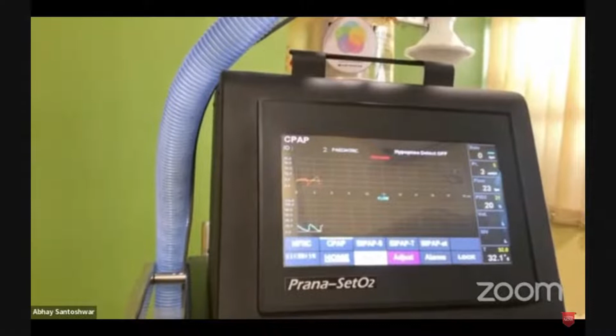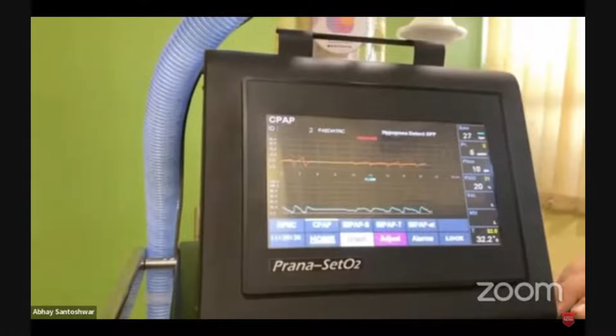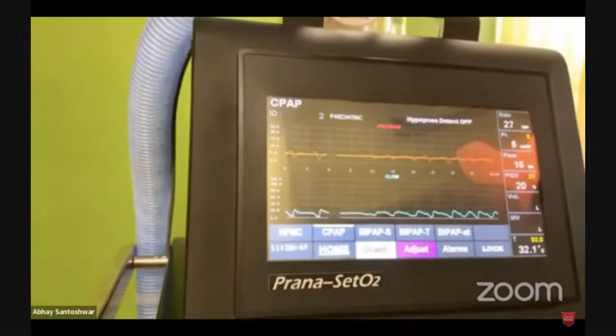So here again, the top waveform, the red one, is pressure and the lower one is flow. As the patient starts interacting, you can see the flows changing and the CPAP pressure diagram showing that it's trying to reach the set PEEP value. You will be able to see on the topmost waveform a yellow line and a red line. Yellow line is the set PEEP value and the red line shows exactly how the patient's lungs are interacting.